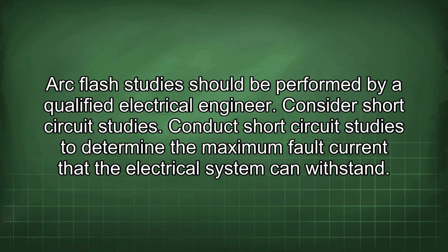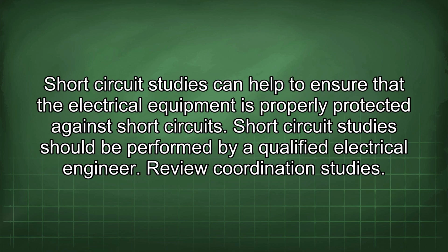Consider short circuit studies. Conduct short circuit studies to determine the maximum fault current that the electrical system can withstand. Short circuit studies can help to ensure that the electrical equipment is properly protected against short circuits. Short circuit studies should be performed by a qualified electrical engineer.